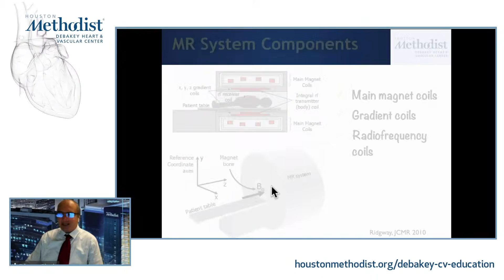So this is showing you the three basic components of an MRI system. It's basically the main magnetic coils, and you can see that in this schematic right here. For those of you that remember that first MRI image that I showed you, the picture of the MRI scanner, the main magnetic coils are actually within this main scanner itself, what people oftentimes like to refer to as the donut. There's also gradient coils, and these gradient coils are also within the main MRI scanner. And then there's radio frequency coils. So let's go through these one by one in a little bit more detail.